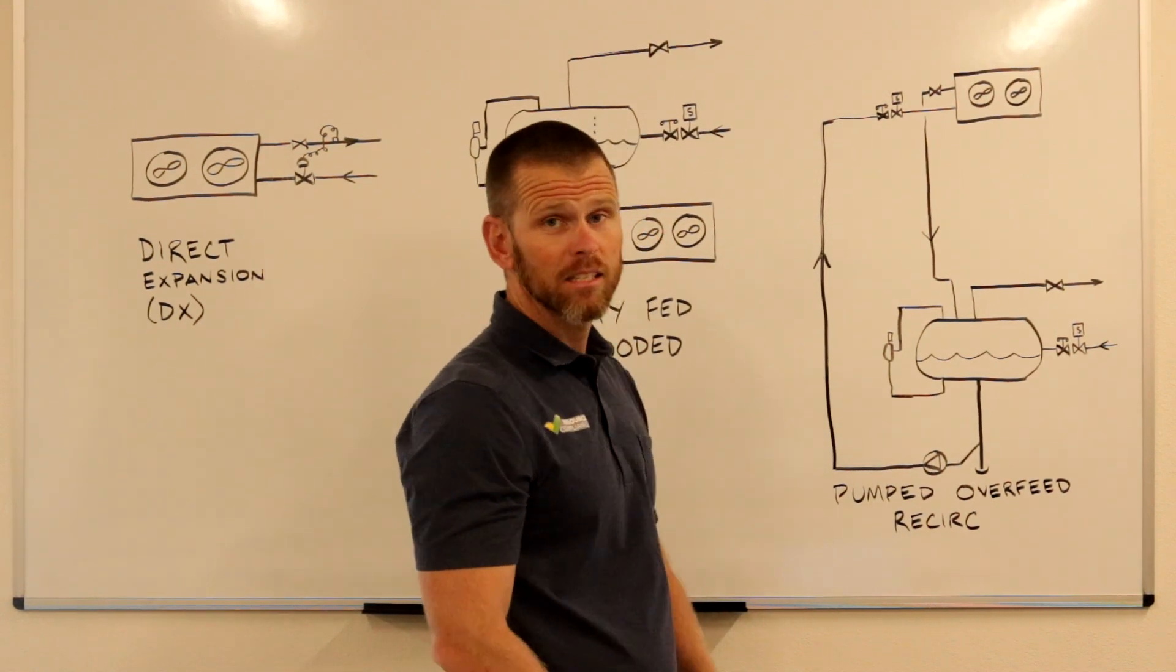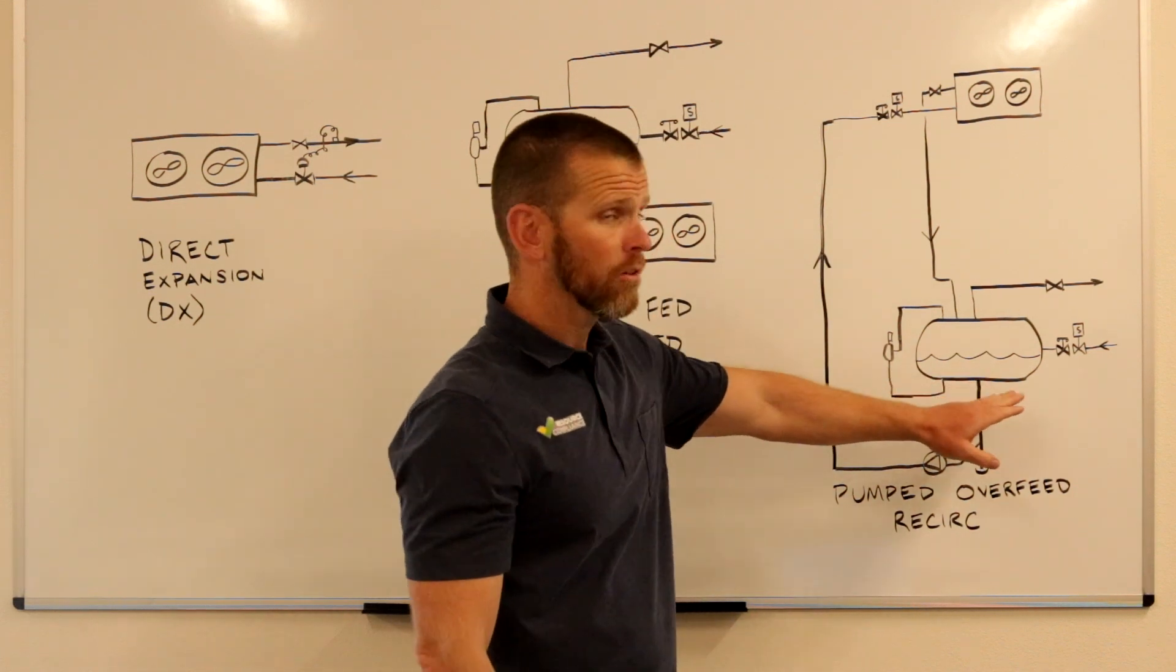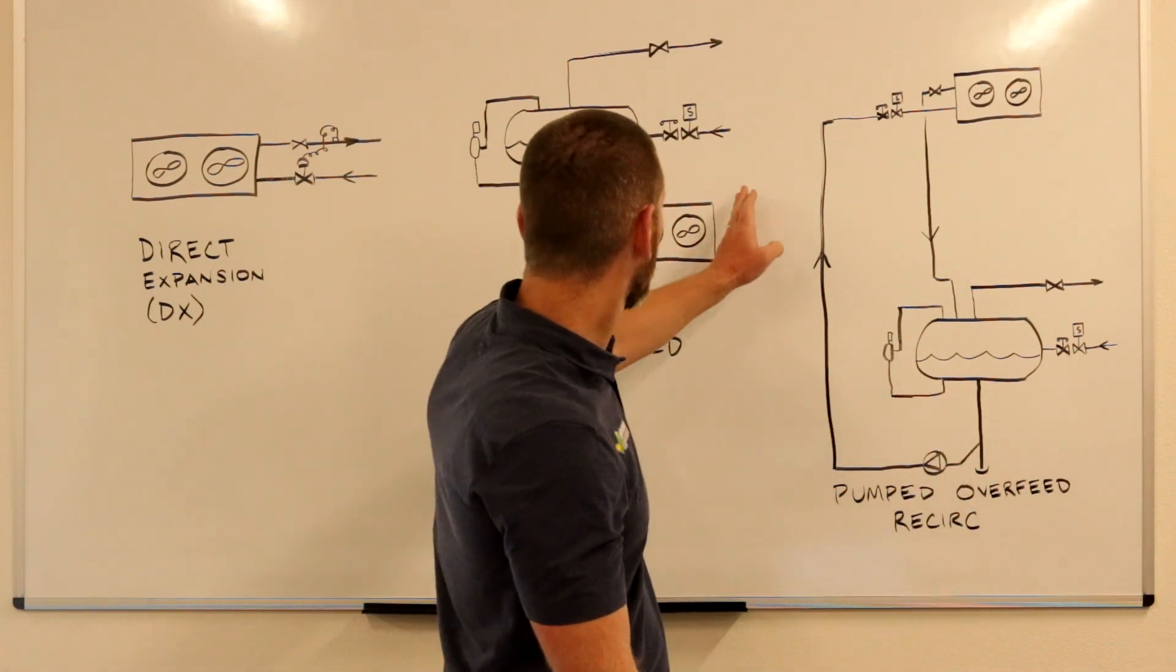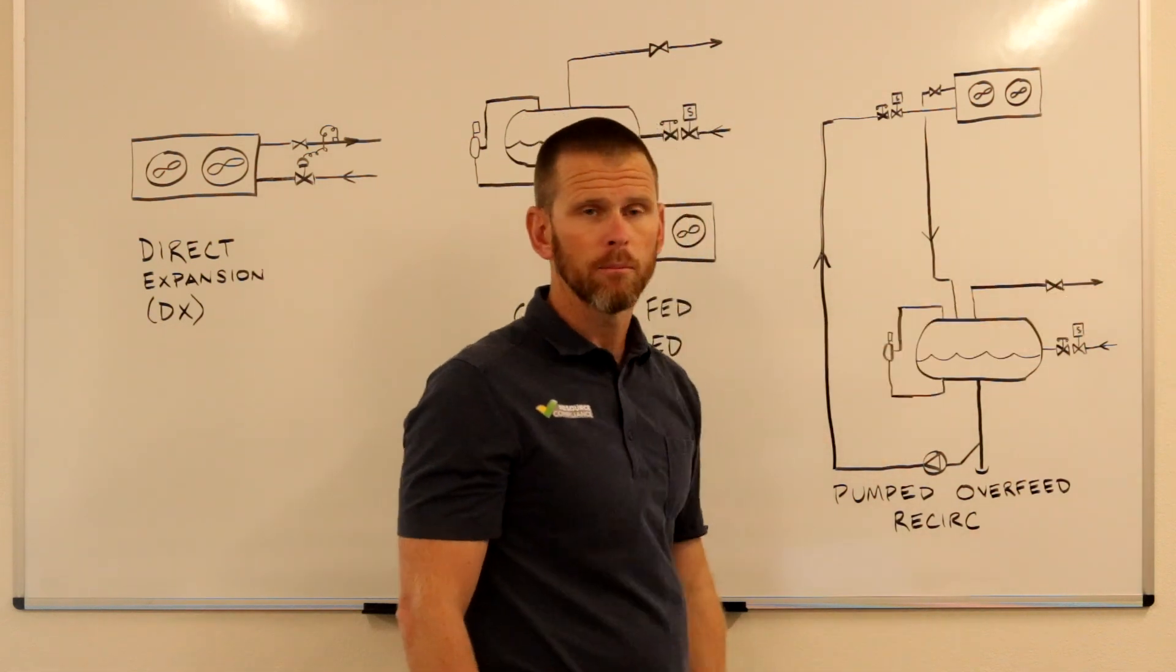So the advantage of this pumped overfeed system is that it takes care of the flash gas situation, just like the gravity flooded system does, because the flash gas is able to be piped directly back to the compressors.